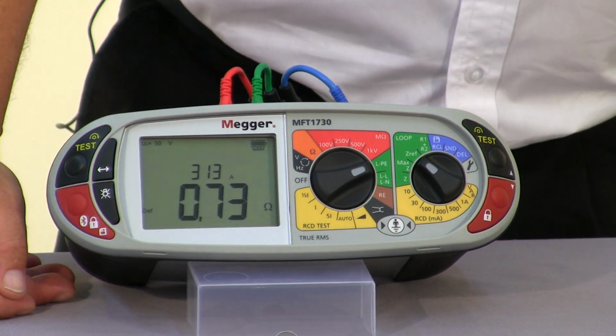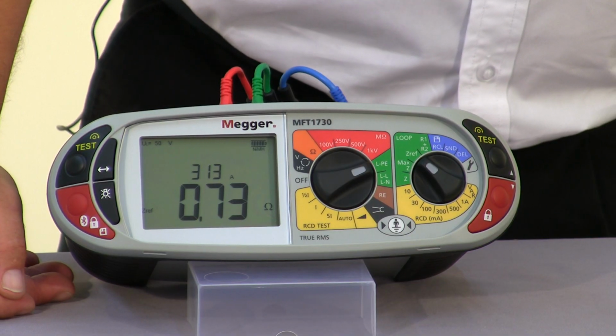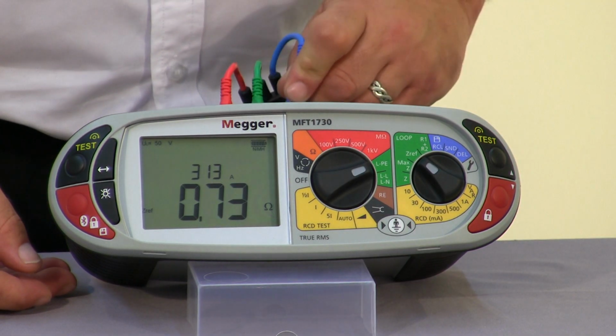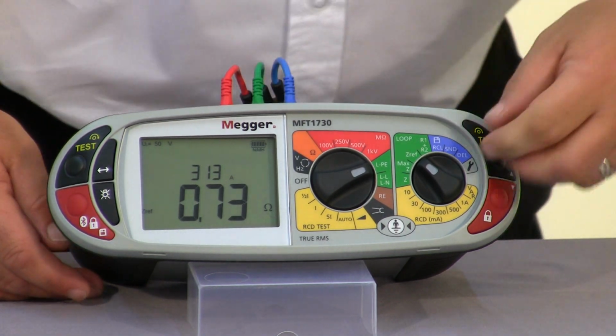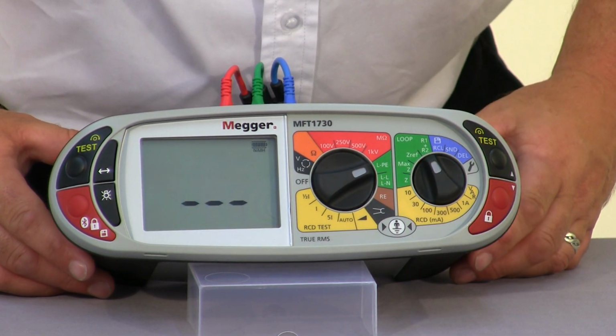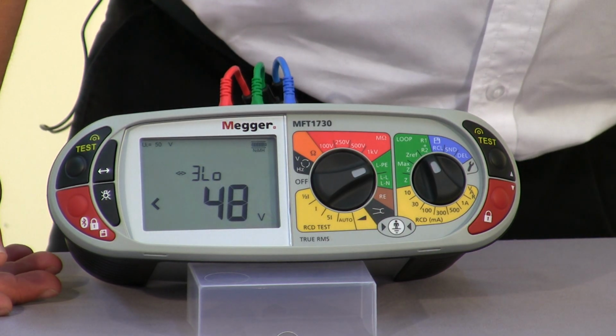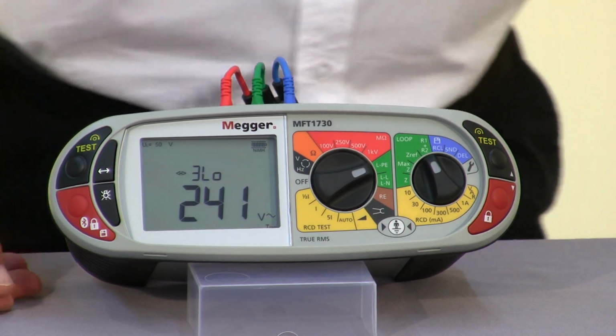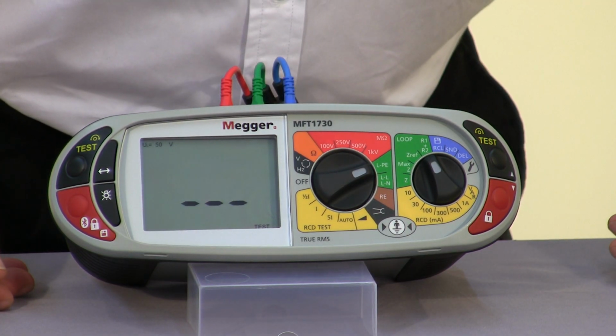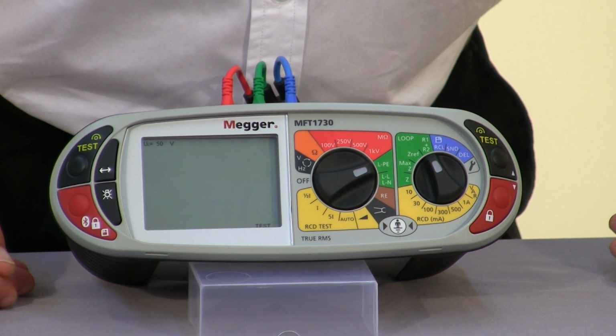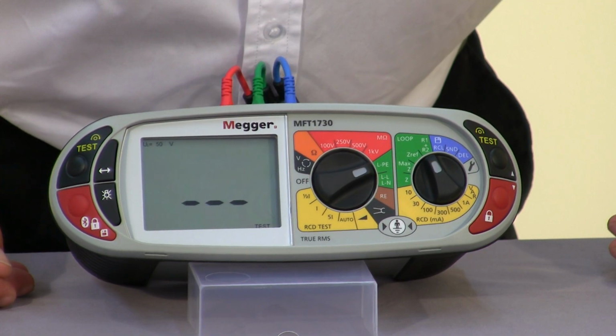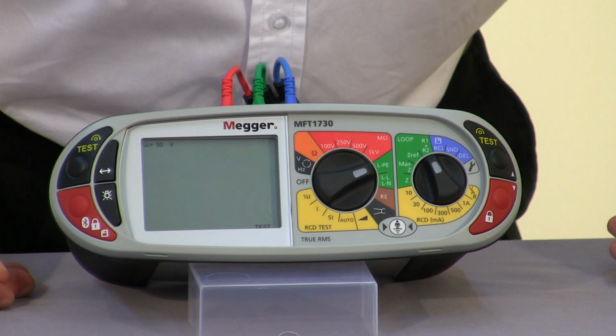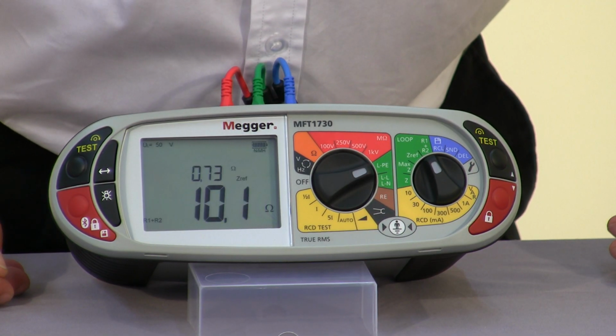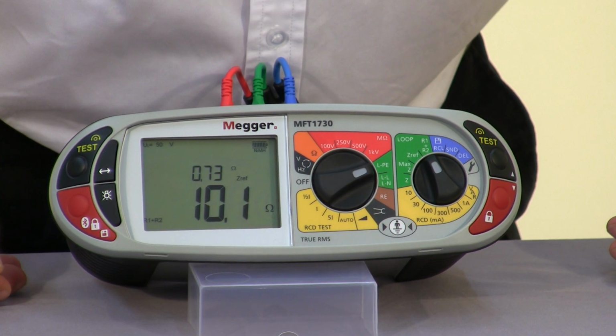So now, without turning the unit off, we will connect for a three-wire no-trip test, and we select our R1, R2. Again, plugging the unit in. So this is our ZS at our socket. The ZREF, which was our ZE value, which we've now saved on the unit, will be deducted away from the second reading. So as you can see, it's indicating the Z reference at 0.73, and it's given us a value of 10.1.